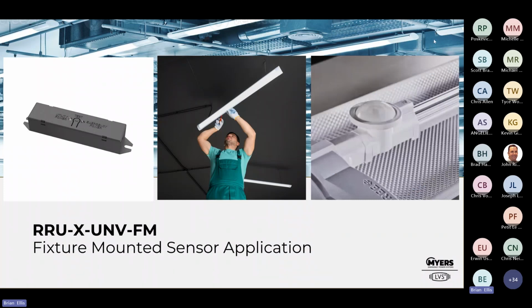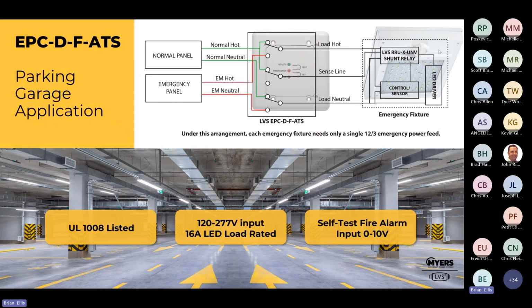Is parking garages, right? So what is pretty commonplace today for a parking garage is providing the emergency and normal fixtures with the integrated occupancy sensor. One of the issues that you have there is anytime you have an emergency fixture with an LED array and LED driver, and you use a control device, you have to have a shunt relay inside that fixture telling it when utility drops out to ignore the control. And the problem with that is you have to feed those emergency fixtures with utility and emergency power. So that's a lot of conduit, a lot of wiring.